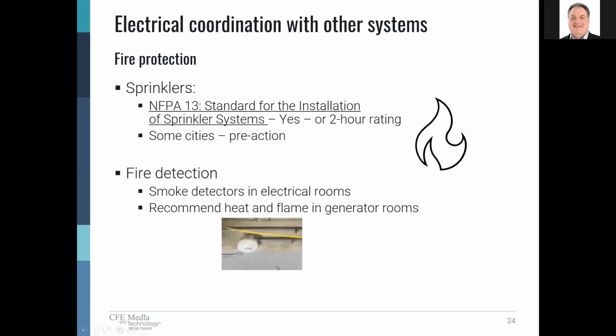Next, let's talk a little bit about fire protection. We get this question a lot. Do you want sprinklers in electric rooms or not? Do you have to? Basically, NFPA 13 says that sprinklers are required, or you have to have a 2-hour rating. This doesn't mean you can't have both. And there are some local jurisdictions that may want to do something different, but this is a general rule. Yes, you need them, or you need to create a 2-hour rated room.